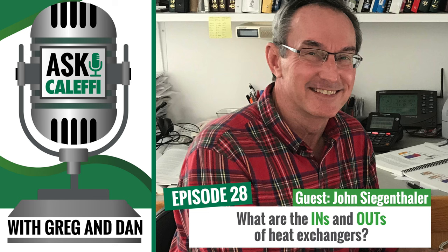One of the things I have asked sometimes is kind of a pushback against the use of brazed plate heat exchangers in domestic hot water. Somebody will say, well, if I have hard water, I'm going to scale up that heat exchanger. And they're right. Absolutely. But you're going to scale up any heat exchanging device if you have hard water. So if you think that using an indirect tank is somehow going to protect you against that without dealing with the hardness of the water, you're going to be very mistaken. What will happen with those indirect tanks is they will scale up if you have hard water.